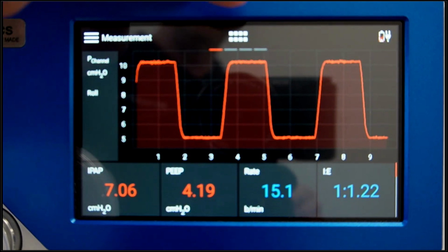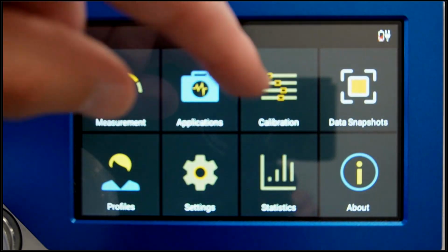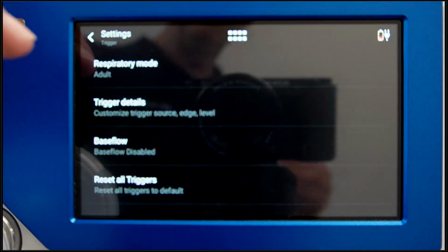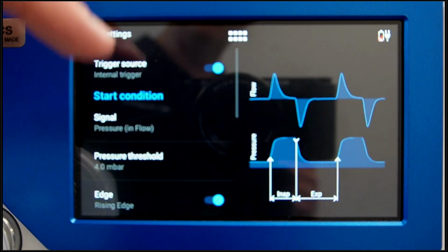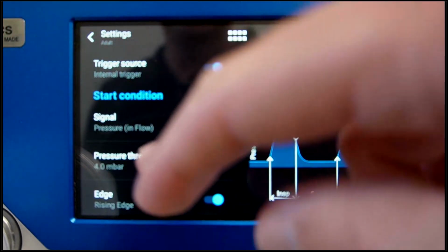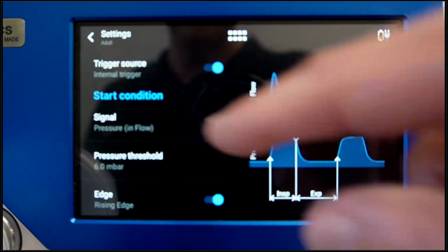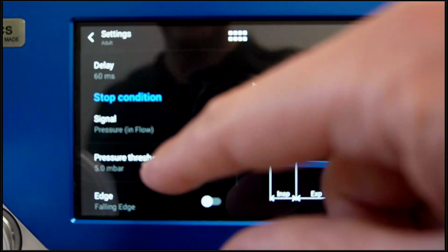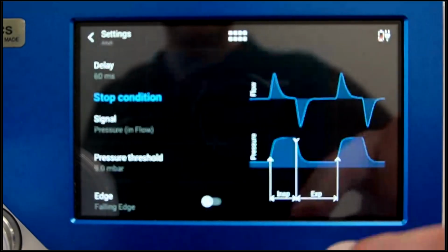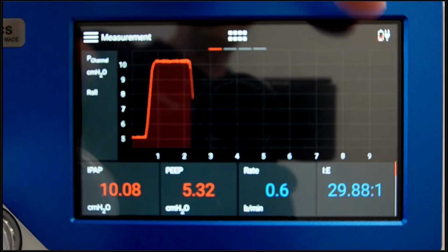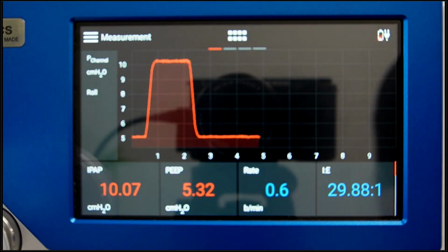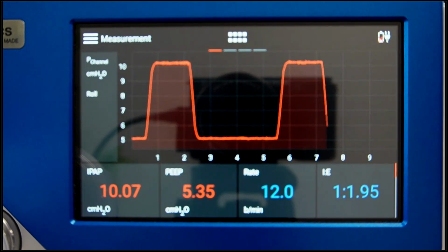So what I would have to do here to resolve this is I have to go into my settings and move my trigger settings up along with my IPAP and EPAP settings. So my EPAP is now 5, so I'm going to set my start trigger to 6, and my IPAP is 10, so I'm going to set my stop trigger to 9. And as soon as I did that, I go back to my measurements. You can see now the gas flow analyzer is again able to trigger and can again measure the breath-based parameters.